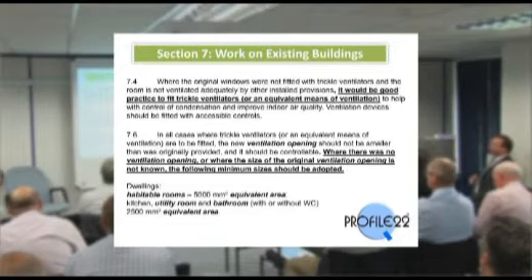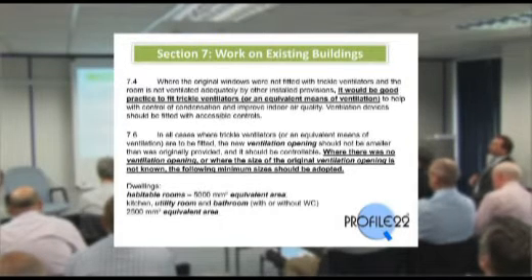We will do the easy part first: work on existing buildings. From a background ventilation point it has changed very, very little in the 2010 regulations. Obviously, for like-for-like replacements, if there are ventilators fitted there now and you are replacing a window, you must fit the ventilators into the new windows.